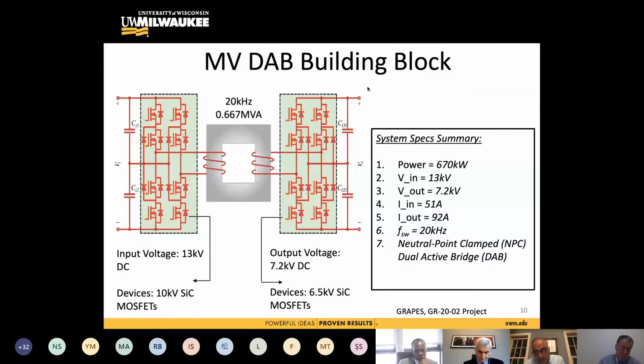And then on the left, you can use 10 kV silicon carbide devices, which have been researched for several years. They are not commercially available, but they are being built by several universities, especially by our partner, University of Arkansas. They built 10 kilovolt switch silicon carbide devices. Then on the right-hand side, you would use 6.5 kV silicon carbide devices. The transformer is at 20 kilohertz, single phase, at 670 kilowatt. And then the whole system becomes a 2 megawatt system.